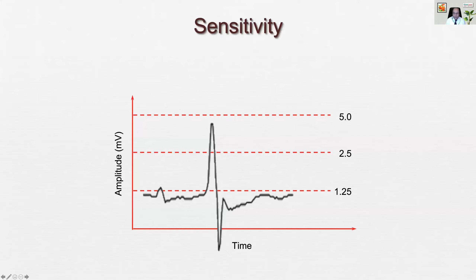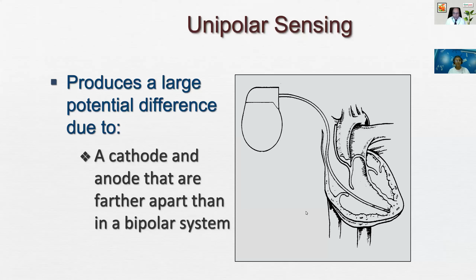If we keep even lower sensitivity, which means a higher value of 5 millivolts, then nothing may be sensed in this example. So 0.5, then everything may get sensed. So we have to keep an optimum sensitivity by sensing, which is a very small circuit, so I may not be affecting it much.